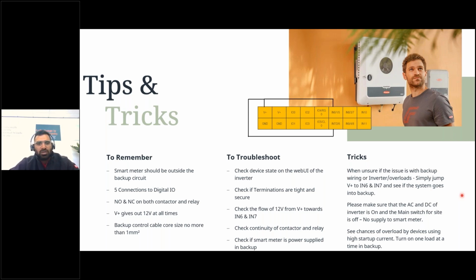And coming to a little trick that you can perform. If you are unsure whether the backup wiring is the issue or the inverter is the issue, you can take 2 little jumpers and directly jump from V+ to IN6 and IN7. So we are kind of tricking the inverter into thinking this 12 volt has come back as feedback on contactor and relay directly to IN6 and IN7. Normally, if the inverter is fine, then the whole system goes into backup. So please make sure that the AC and DC of the inverter is on and the main switch for the site is off, so no supply to the smart meter.